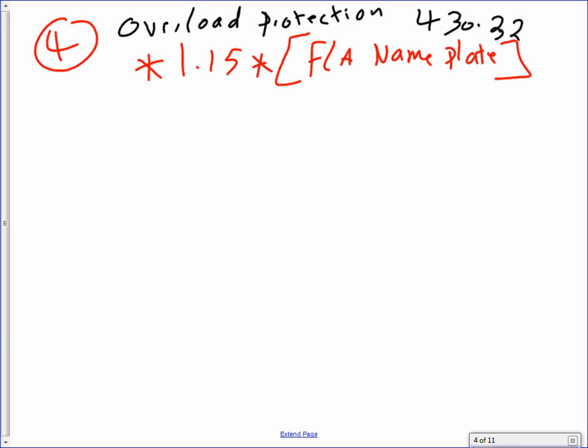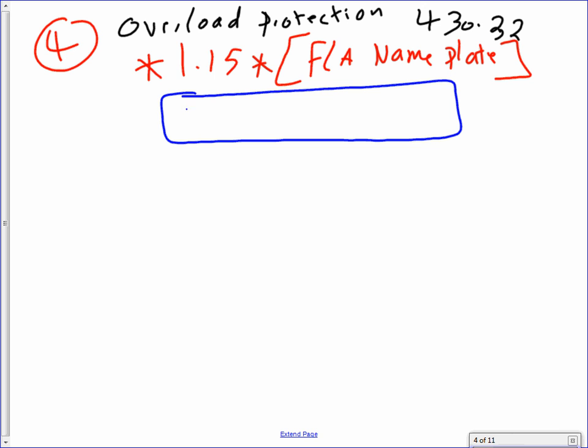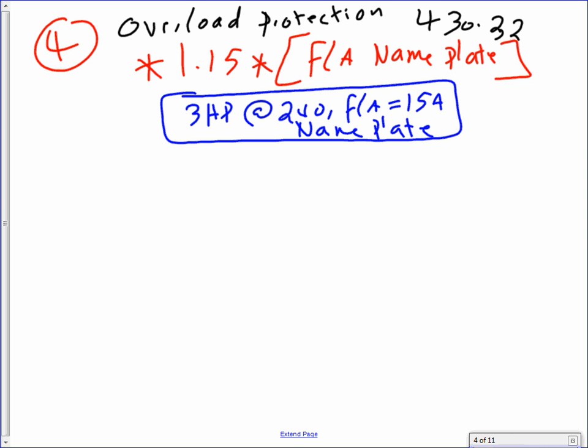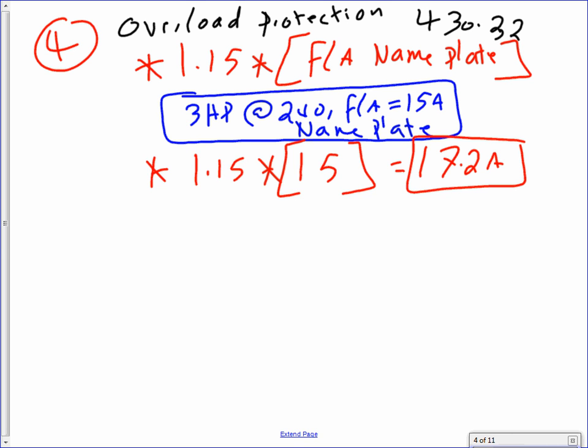It's not 17. Okay, now I have to give you a disclaimer here. Say it's a 3 horsepower motor at 240, full load amps equal 15 amps. This is my nameplate. I have to give you this information right on the nameplate. Because I gave you this info, then you can continue. You take 1.15 times 15, that will get you a healthy 17.2 amps. And that's how you're going to set your overload.